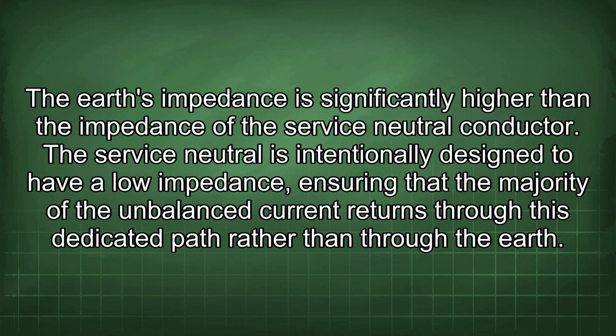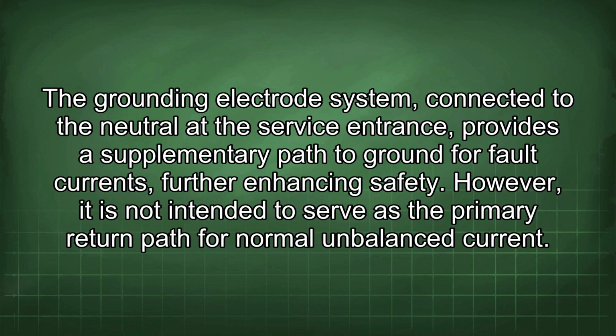The Earth's impedance is significantly higher than the impedance of the service neutral conductor. The service neutral is intentionally designed to have a low impedance, ensuring that the majority of the unbalanced current returns through this dedicated path rather than through the earth. The grounding electrode system connected to the neutral at the service entrance provides a supplementary path to ground for fault currents, further enhancing safety. However, it is not intended to serve as the primary return path for normal unbalanced current.